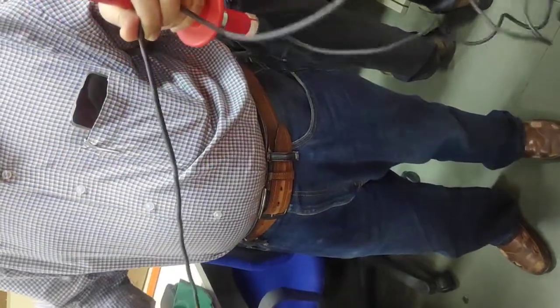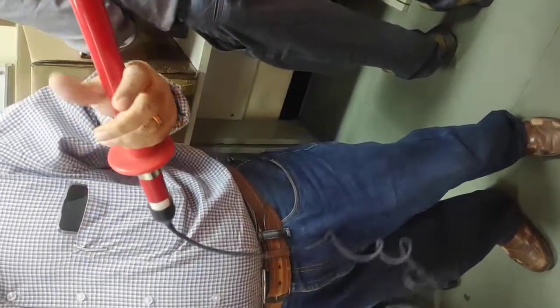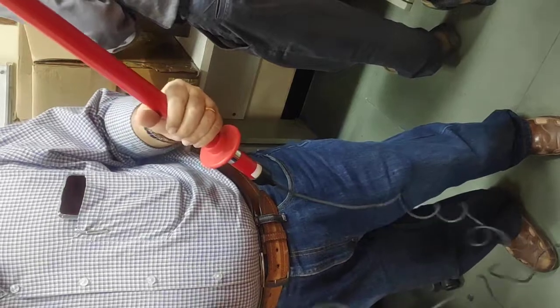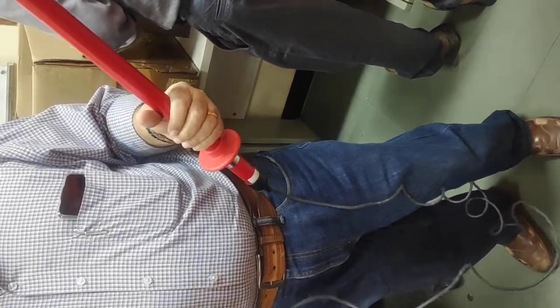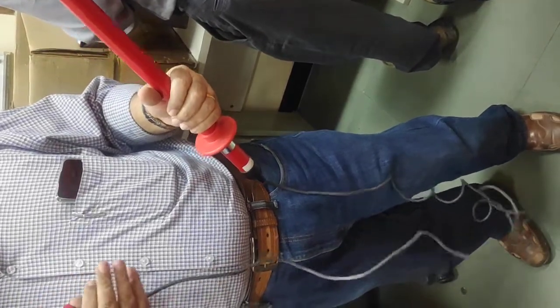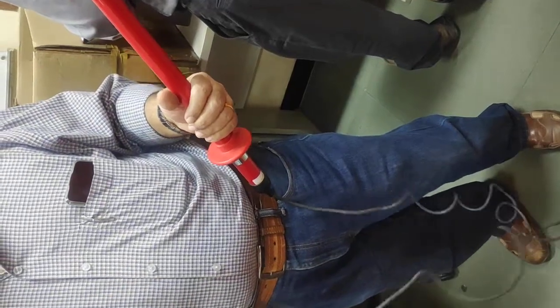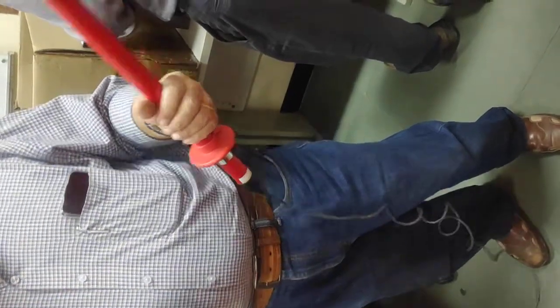Then there is one more tester which will detect the voltage, and at the same time if there is some residual voltage still there - of course not 6 kV, so 500-600 volts - it will ground it, it will discharge it also.